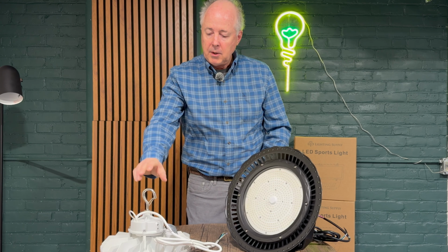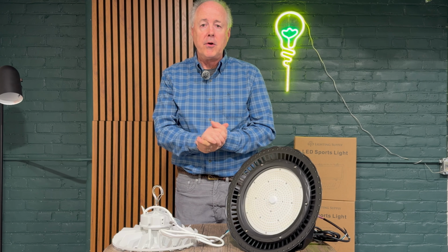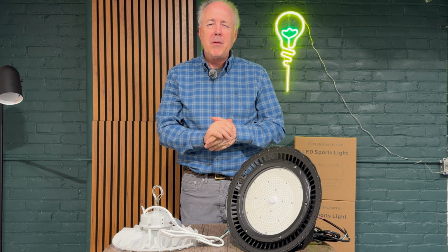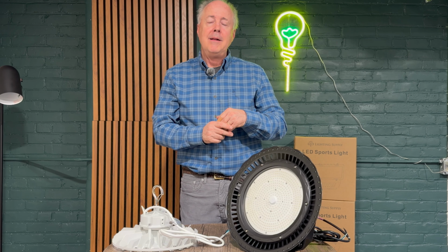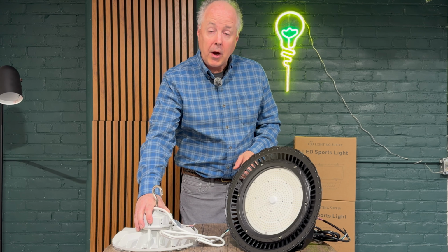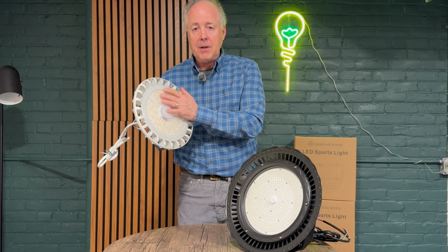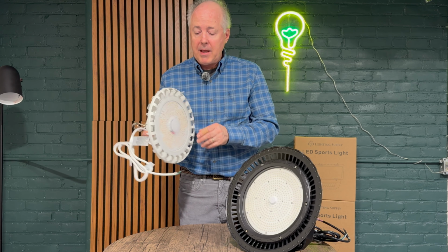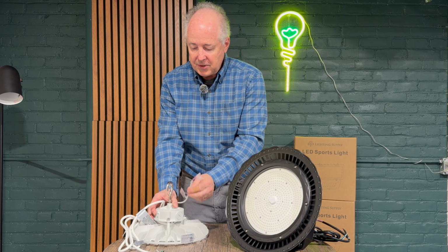Commercial lights are used where your mounting height is probably not over 30 feet. It's a warehouse, it's a shop, an environment where there aren't any extreme conditions. It's not cold, it's not hot, it's not wet. All your commercial UFOs are IP65. They come with a nice optic, which can be a 120, 90, or 60 degree optic, or a frosted lens. They're all designed to take motion sensors, and they come with dimming wires.